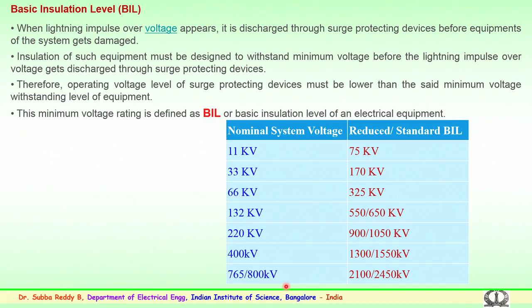So, for 400 kV, 1275 or 1300 kV is a reduced value, and 1550 kV is the specified BIL for the 400 kV systems. And for 800 kV or 765 kV systems, the value of the BIL is 2100 and 2450 kV respectively. So, any equipment which is manufactured has to be designed for the basic insulation level, so that the equipment performance is not disturbed because of the surges which it encounters in the field.